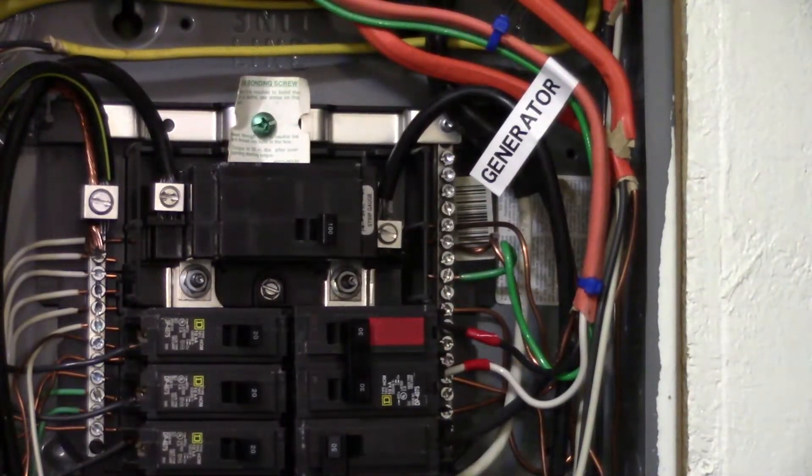I've run my cable to my dedicated circuit breaker in the box. I've marked it with label tape, and it's the one that has the green wire with it. I also have it indicated by some blue tie straps to draw attention that it's something a little different in the box. Also on the breaker, I put some red tape, so with the red tape on the wires and red tape on the breaker it should be a no-brainer if somebody opens this panel other than myself.